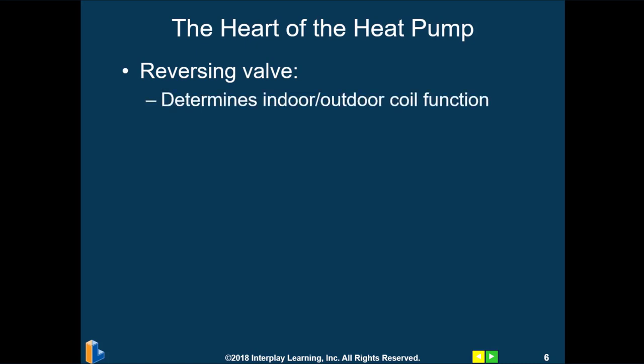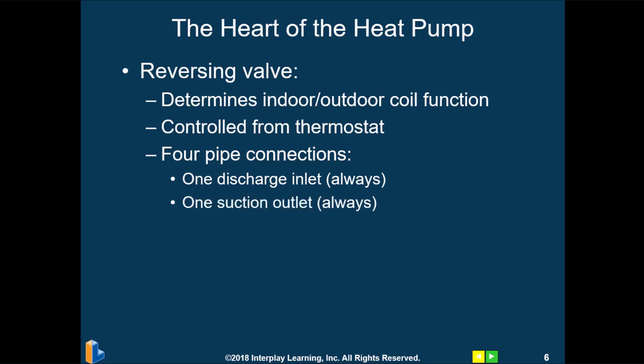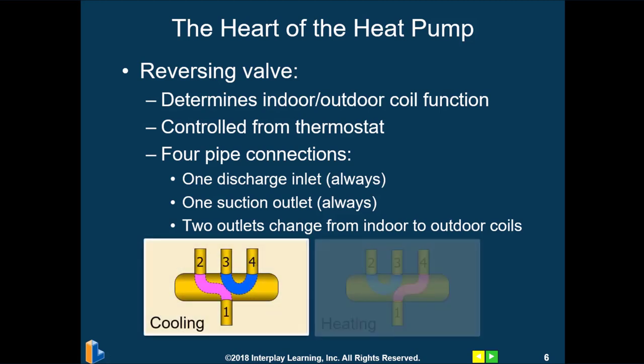The heart of the heat pump is the reversing valve — this determines whether the discharge gas gets sent to the indoor or outdoor coil. The thermostat also has an impact; there is an O terminal or sometimes a B terminal that controls the position of the reversing valve. The reversing valve has four connections. The lone port on the bottom is the discharge line — the permanent discharge port, always receiving discharge gas from the compressor. The center port of the three at the top is the permanent suction port, always feeding suction vapor to the compressor. The two outside ports change functions and route gas to either the indoor or outdoor coil, depending on whether we're calling for heating or cooling.